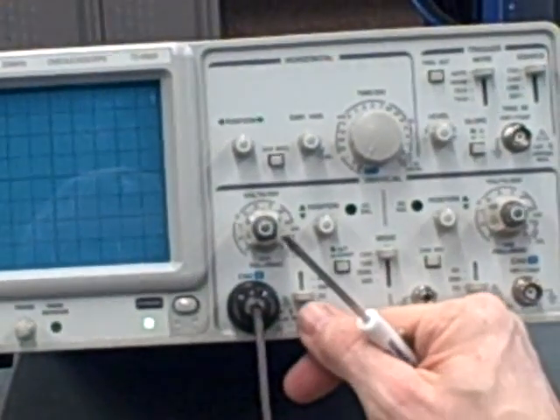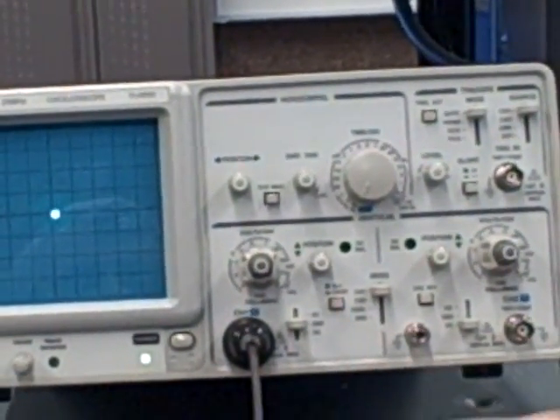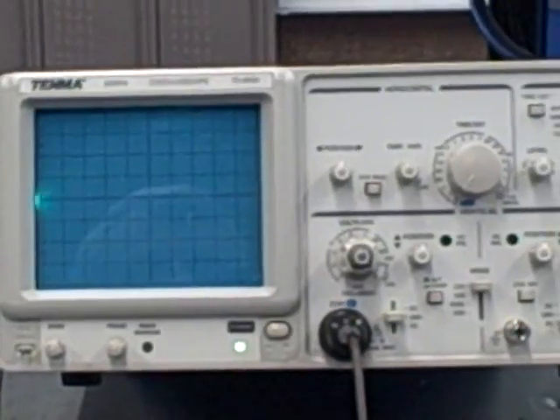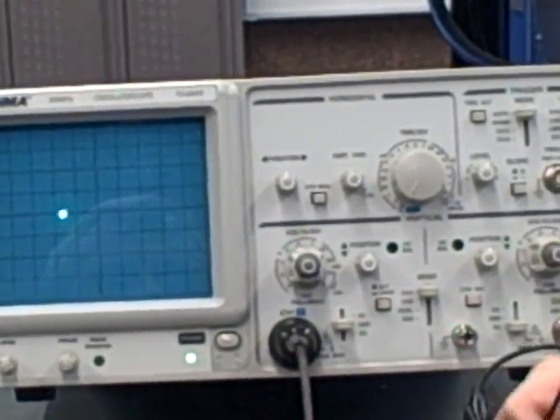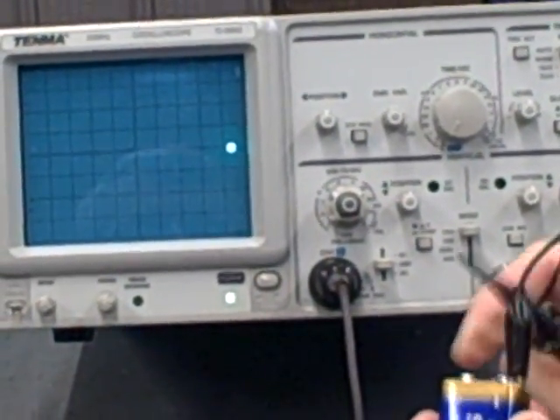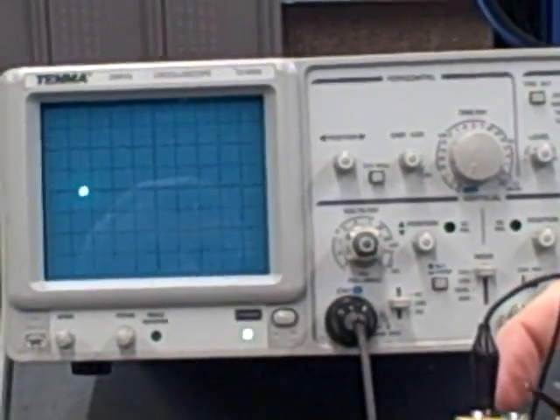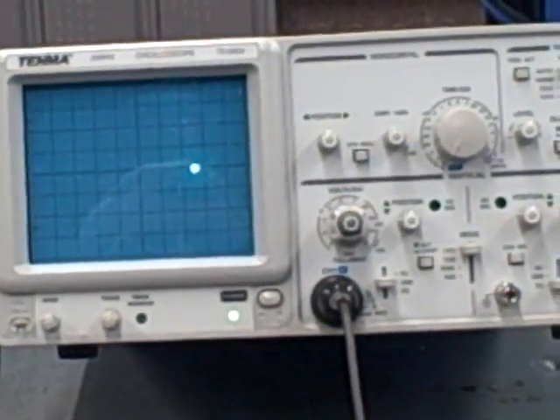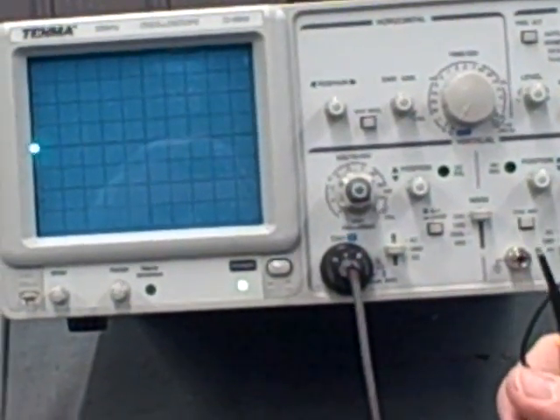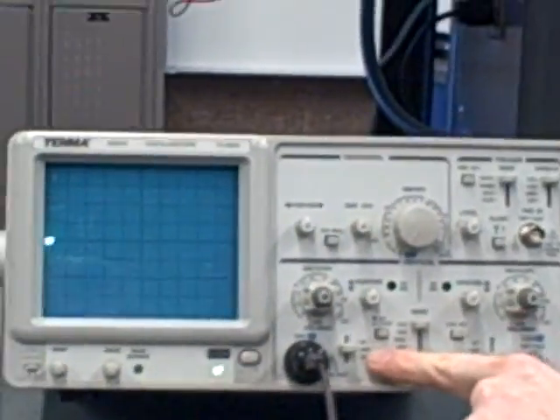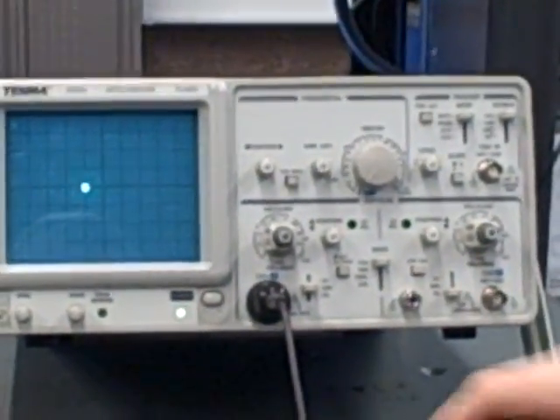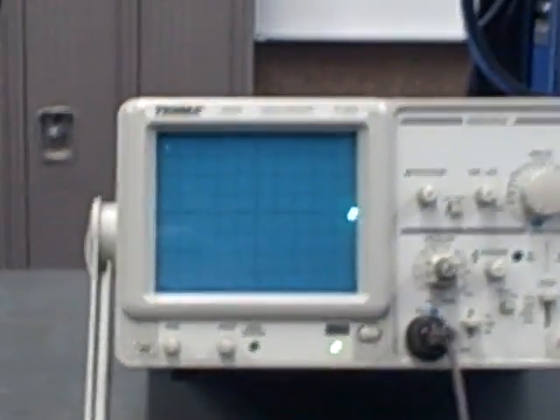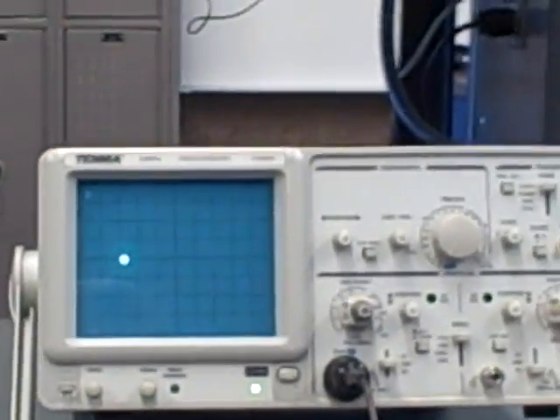If I set it to the ground position and I try reconnecting my battery, we're going to see a whole lot of nothing. Absolutely nothing happens. I reverse the polarity, and nothing happens there either. There may be times where I have a signal applied to the input of the oscilloscope, and I want to basically turn that signal off and just see where my zero point is. I can do that by switching to the ground position. Or if you're feeling devious, you can play tricks on other people and switch to the ground position and see how long it takes them to realize that.